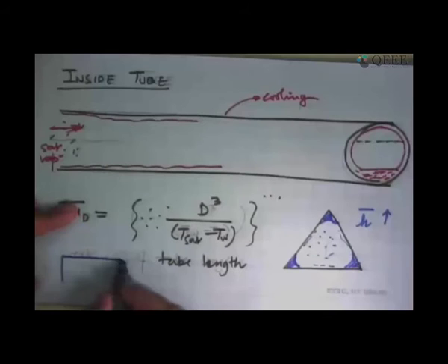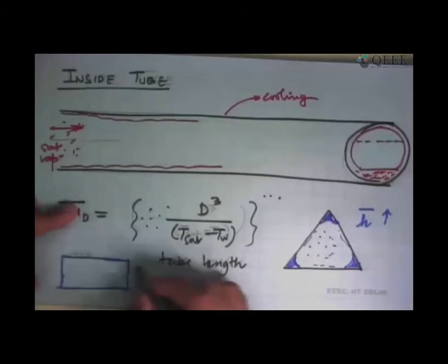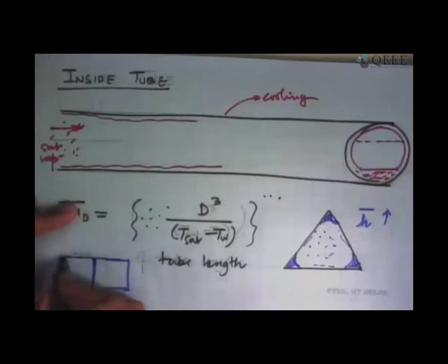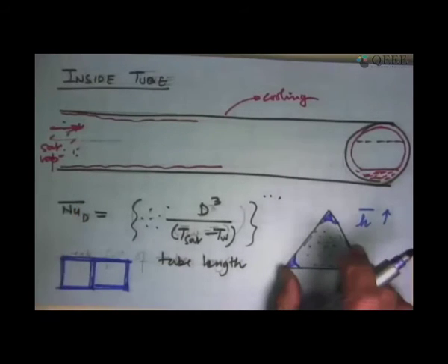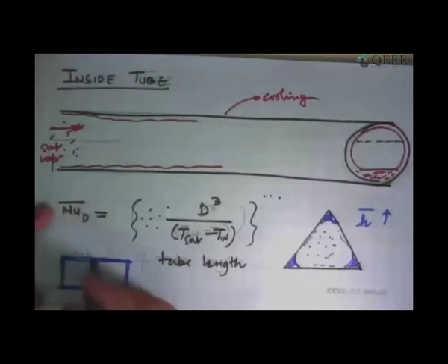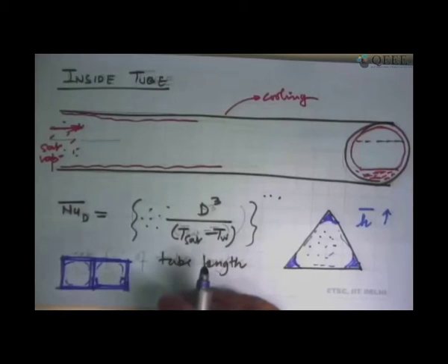Either this, and there are examples that you can see in the market, as you can see in some air condensers. The tubes are made by making them into walls which are, say, square, and it now depends on the convenience of manufacturing. This may not be very easy to manufacture, this may be easy to manufacture. And when you do that, liquid will get captured in the corners and you will get a much better heat transfer coefficient from these. So these are already in the market.